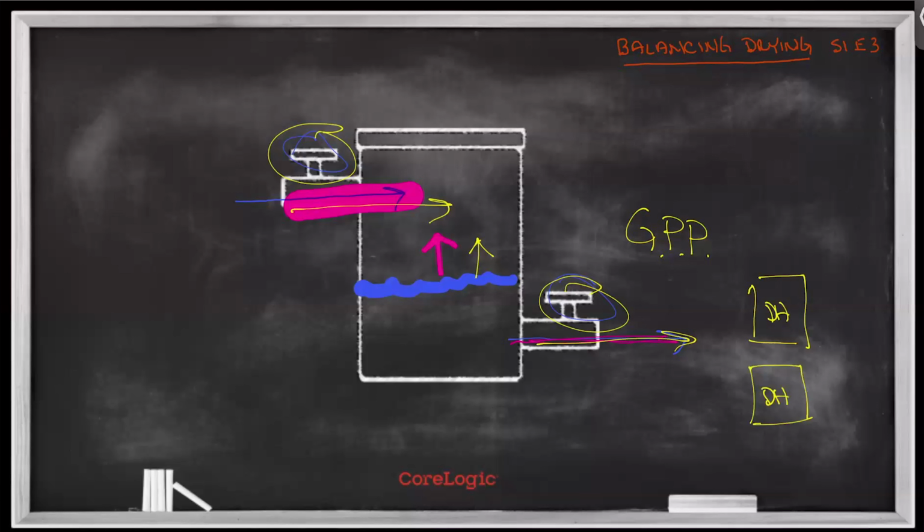Okay. And I'm going to say that again because it's really important. Our automatic reaction is typically just add another dehumidifier. And most of the time, that is not the most appropriate action. To understand what I mean by that, we've got to analyze these levers. All right. So let's first talk about the lever that's letting water into the air, right? This rate at which water is being added to the air can be coming from a couple of different sources.